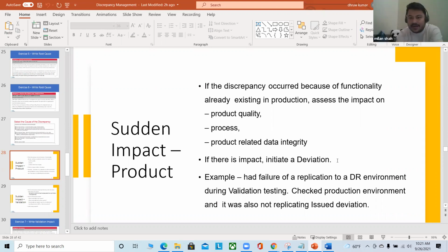Yeah, I have a question, sir. Yes, go ahead. While in the production process, if the label printer doesn't print, like 1,000 pages, does it come under CAPA or what? Since it can become your deviation, yes. And a deviation can turn out to be a CAPA. On what factor does it affect: quality, process, or data integrity? What do you think it affects? Product quality. But it is still printing. It is still printing my resolution, what I'm expecting. So the process, you have a process defect.